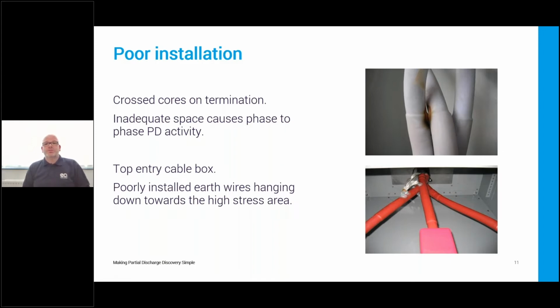So on to poor installation. We've got a couple of examples here, both cable related. On the top picture there, we can see some cross cores on a cold applied termination by the looks of things, where inadequate space has been left between the phases above the crutch, which has resulted in phase-to-phase PD activity. On the bottom picture, we've got a heat shrink termination going into a cable box where the earth wires have been pretty carelessly left too close to the high stress area of the termination, which again has resulted in some PD activity. So poor installation is quite a common cause.